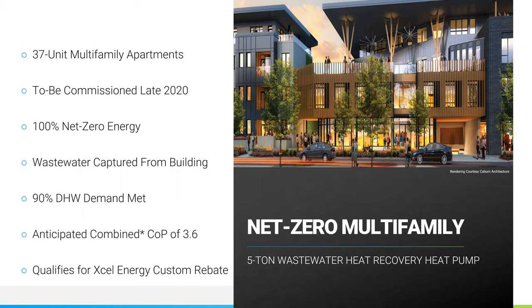So no matter what, year round, they're anticipating a coefficient of performance of about 3.6. Putting that into perspective, 3.6 is actually about 360% energy efficient. Some would ask how do you get 360% energy efficient? That's because for every one unit of electricity we're putting in, we're putting out 3.6 units of heat energy to that domestic hot water loop. So our device is making the energy coming in more efficient through the heat pump refrigeration process. So that's how we're getting more efficient.